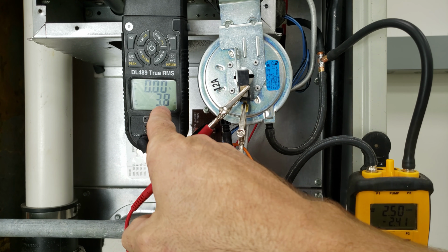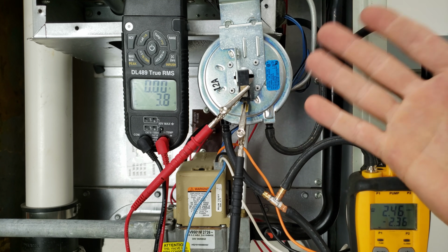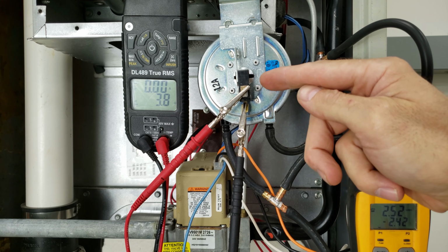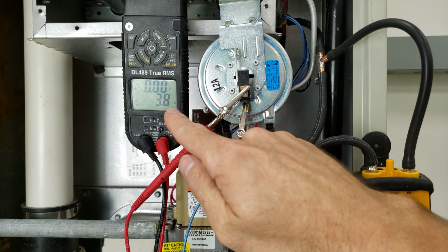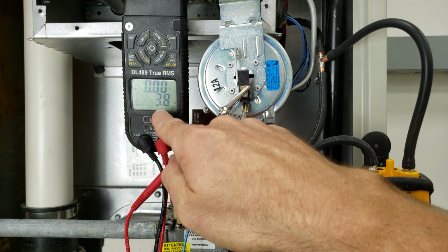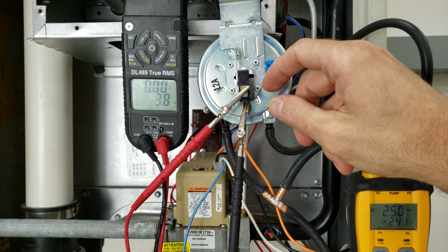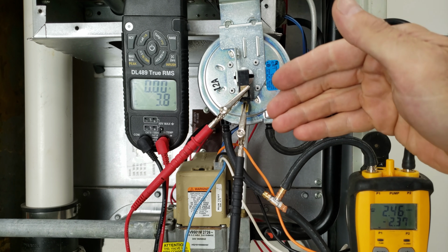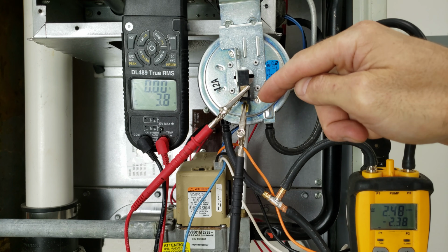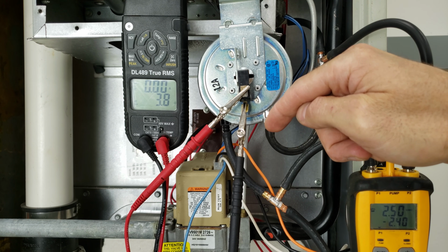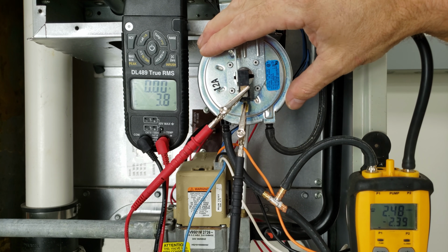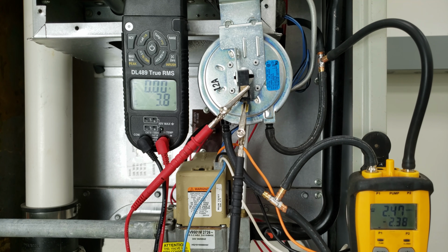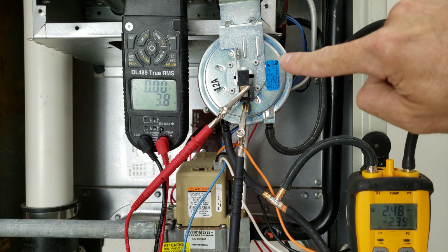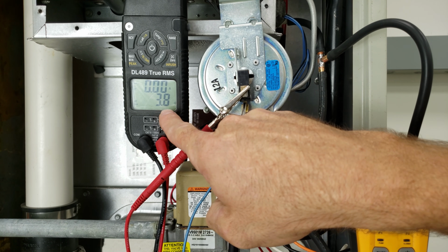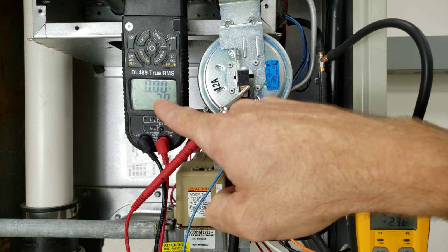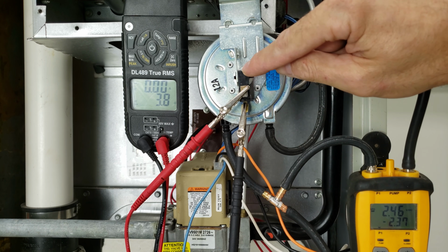We're measuring with our multimeter across this switch. It's actually closed right now, but it seems that our contacts on our pressure switch are pitted, and so we're measuring electrical resistance across that switch. If the resistance is high, it's not going to allow the proper amount of electrical power across the switch in order to prove that the inducer motor is running and that there's no problems. So in this case, we would still replace this pressure switch because we have a high electrical resistance. We should be measuring very close to 0.0 ohms of resistance when the switch is closed.